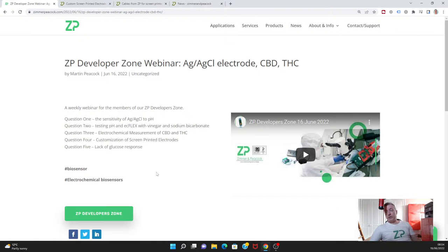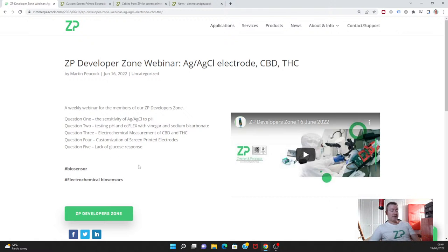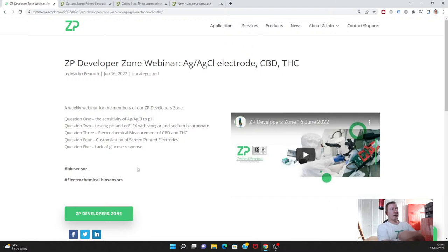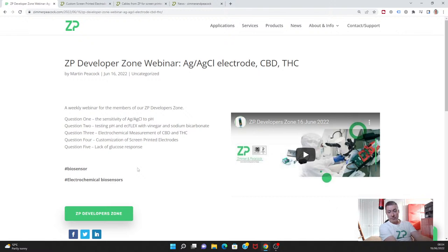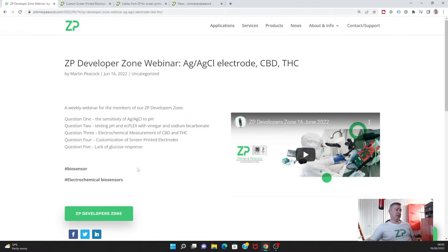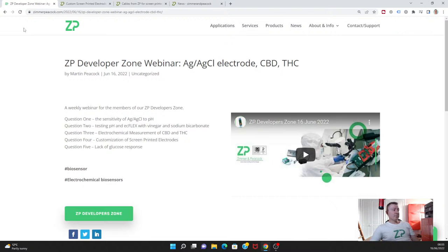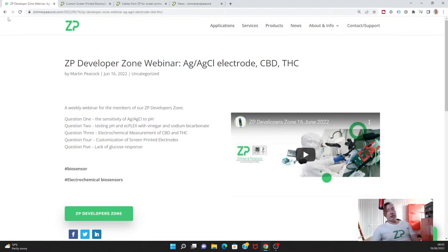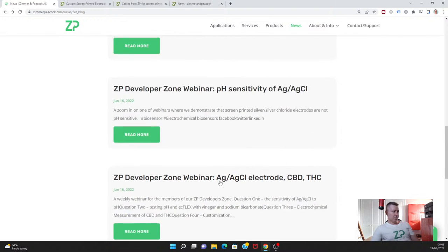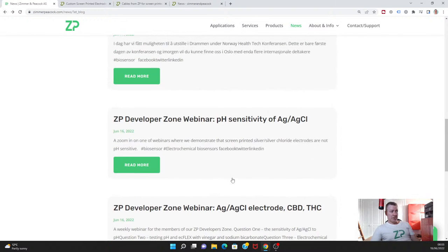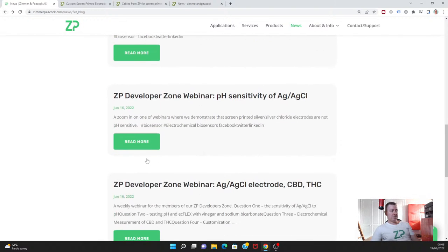These are the materials found in hemp. We also talked about the customization of screen printed electrodes, which I also have a philosophy that it's best avoided. There are ways of branding products without necessarily having a completely customized product. Then we had a very interesting inquiry about the lack of glucose response. In the end, it came down to the fact that the team we're corresponding with is using a carbon electrode. An unmediated carbon electrode is not a good catalytic surface for measuring hydrogen peroxide. If you want to make a glucose sensor and it's not working, and you're probably making a generation one glucose sensor, then the material to use is platinum rather than carbon.